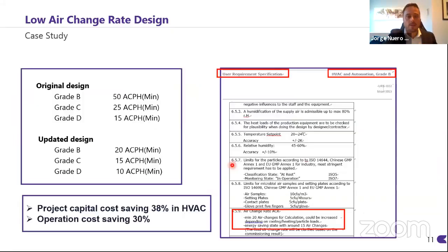So in this example, in the original design, it was designed as grade B with 50 air changes per hour, as is recommended in ISPE for the conceptual design. But during the detailed design, understanding the process and what is happening in every single room, you can drastically reduce the number of air changes per hour and focus a dedicated exhaust system on some points, or increase the speed of the fans when the operator is coming in. We can save a lot of air.